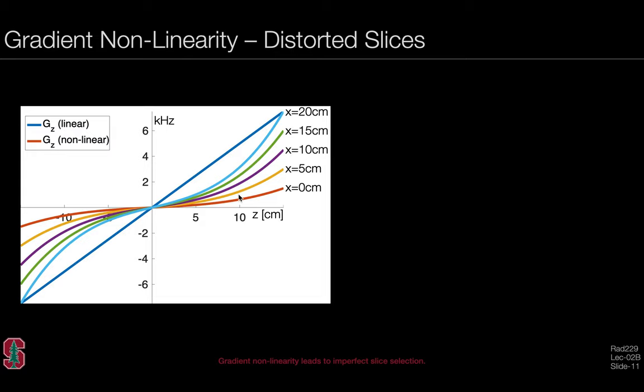What if the distortion is a more general function of space, varying in perpendicular directions as well? It may be the case in the context of a nonlinear gradient that this mapping is a function not only of z, but also of x. We have different nonlinear curves depending on where we are along the x axis as well. This suggests that these nonlinearities are spatially distributed across x, y, and z for a z gradient as well as for an x or y gradient.